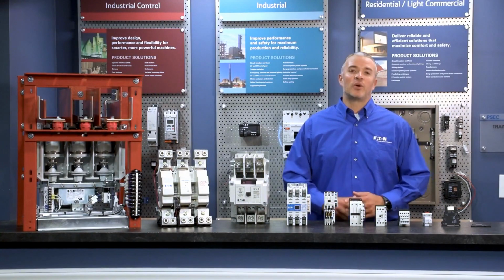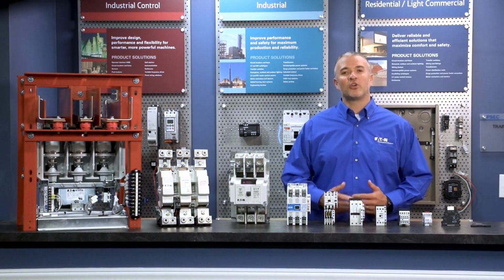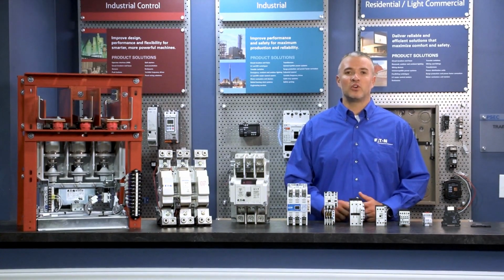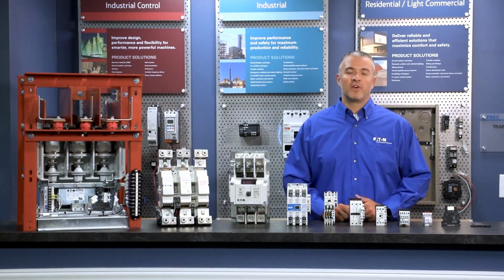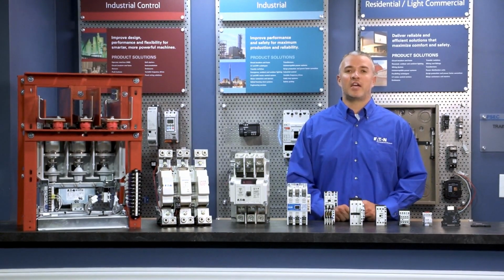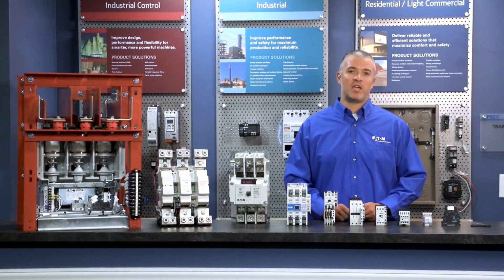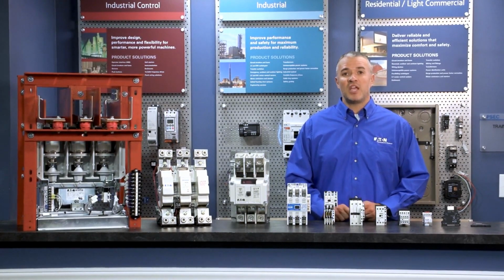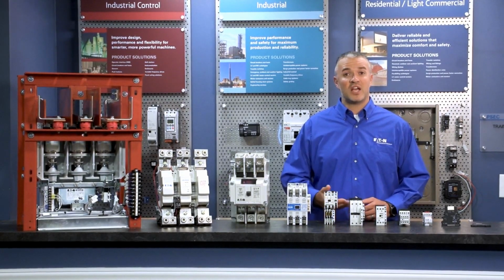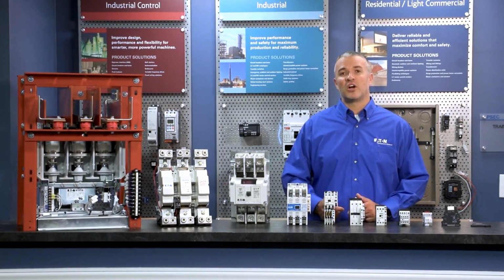Vacuum contactors are magnetically held, but may not yield as many mechanical operations due to fatigue failures of the metal bellows. Whether using a latched or magnetic contactor, choosing the correct size of contactor is critical for proper operation. First, you need to know if you are selecting a contactor for a NEMA or IEC application. The NEMA standard uses a more brute force approach that requires less front-end engineering. Basically, you have this size motor, so you use this size contactor.